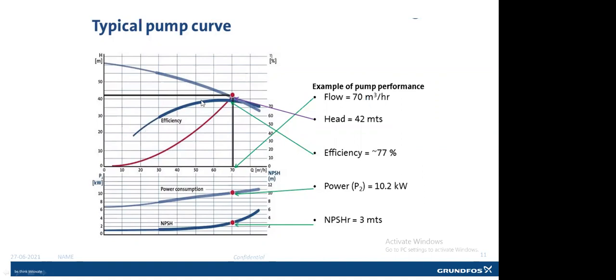And this curve is for the efficiency. So if our duty point shifts to the left hand side of the curve, it directly impacts the pump efficiency. As the duty point shifts to the left side of the curve, efficiency drops. And if the duty point shifts to the right hand side of the curve, another impact comes into the picture regarding the NPSH. So if you consider the NPSH curve, at the design point the NPSH required is 3 meters. And if this pump operates at lower head, let's say for example it operates at 35 meters of head, the NPSH required increases directly to 5 meters.